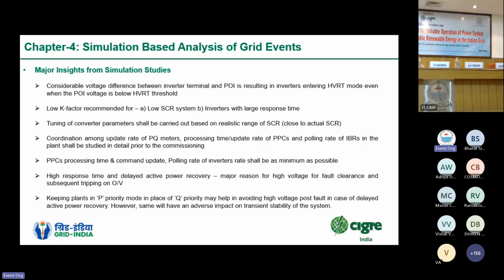So major insights from the simulation studies have been summarized here. It was found that there was a considerable difference between the inverter terminal voltage and the voltage at the point of interconnection. So how was it impacting the system? We observed that even when the voltages at the point of interconnection were within the normal operating range, some inverters within the plant had entered the HVRT or the LVRT curve and started reducing their generation. So this major insight was provided by the simulation studies.